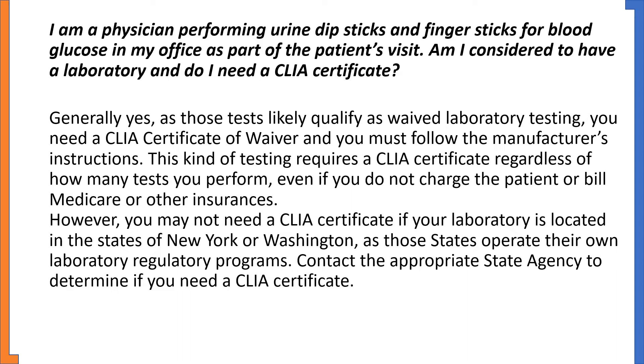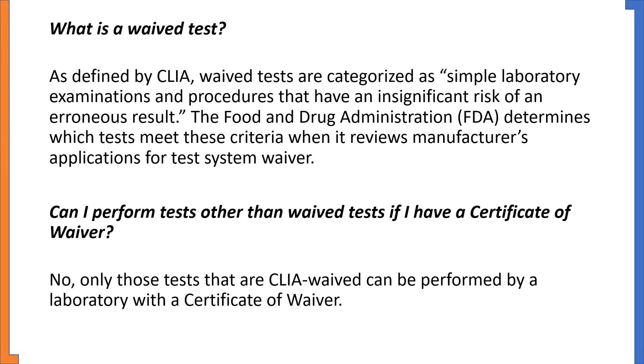This kind of testing requires a CLIA certificate regardless of how many tests you perform, even if you do not charge the patient or bill Medicare or other insurances. However, you may not need a CLIA certificate if your laboratory is located in the states of New York or Washington, as those states operate their own laboratory regulatory programs. Contact the appropriate state agency to determine if you need a CLIA certificate.